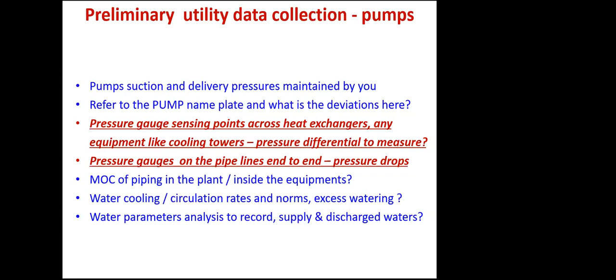The MOC, material of construction of piping, as I said before, is rigid PVC, especially on the water lines, and we are using water circulation. Here I will say, thanks to the gazette notifications, 1 unit of power, 1 kWh, before was consuming 6 to 7 liters of water at the thermal stations. Thanks to the BEE and PAT norms, now only 2.5 to 3 liters of water is consumed to produce 1 unit of power at the generation point.